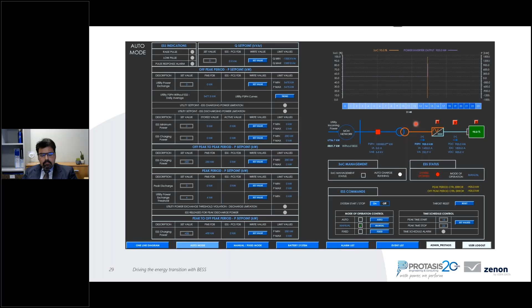In this screenshot is the operating environment of the system for the automatic mode, where the operator sets all the required set points and at the same time is able to monitor the system performance in real time. In the left pane here of the screen, the operator sets the parameters and the set points for the system operation. So actually it manipulates the power plant controller. In the right pane here, are visualized in real time the main parameters of the system, and the operator is able to comprehend at one glance the status of the system.